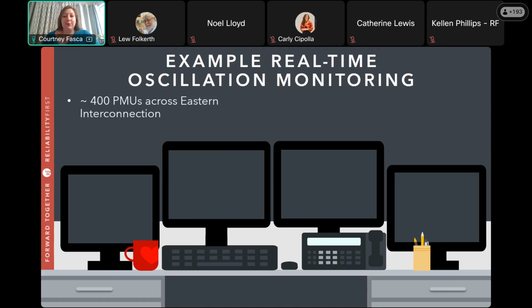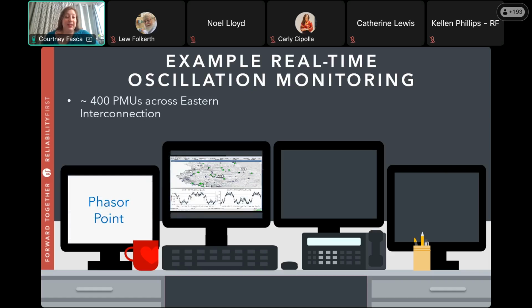So basically, the report describes that the utility took advantage of the high sampling rate of PMUs, like Lew mentioned, to visualize and document the system dynamics in phasor point. The purpose of developing this event detection mechanism was to help control room personnel quickly identify harmful oscillations from the common system variations.